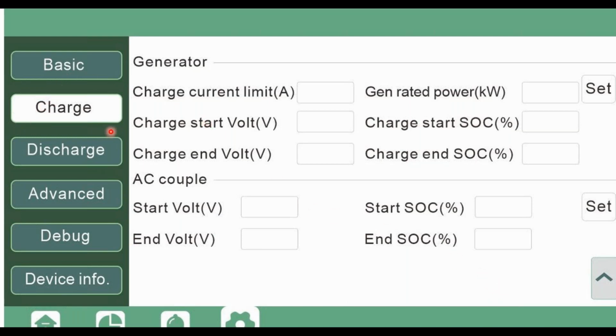And moving on in the same generator functionalities, here we stipulate the charge current limit of the generator and the generator rated power. Now, if you have a generator with a set power rating, we recommend you just subtract 10 percent of that rating, just to avoid any potential throttling, right? You don't want to max out your generator's power capability, as this could result in throttling. So just use 90% of the generator's capability. You can stipulate the generator to start based on SOC, as I said, or end based on SOC. The same with voltage for open loop or lead acid battery applications.